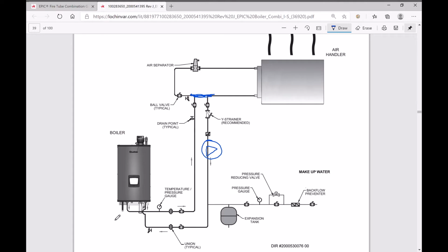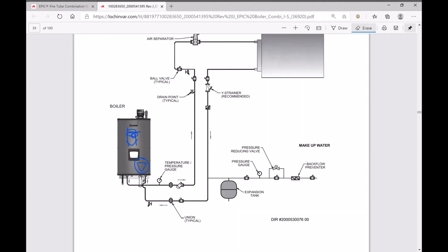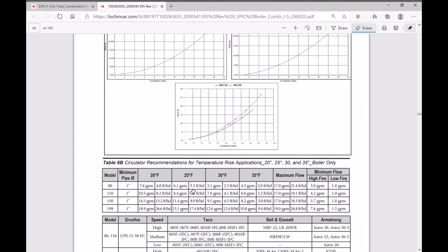But with the low resistance heat exchangers inside these units, the fire tube, if you will, because there's such a little restriction with these units, and on the combis there's a built-in pump, we can actually get rid of these closely spaced tees and this additional pump here. And so that's what we're going to talk about. There's a reason why in our manual we show that we can pump directly out of their unit into the air handler and back to the unit.